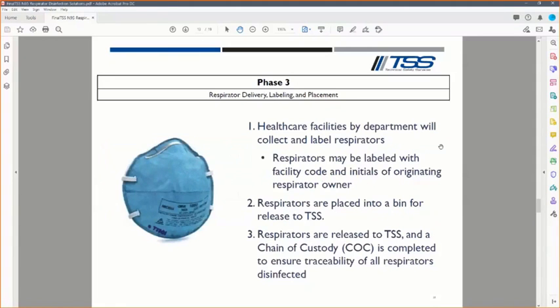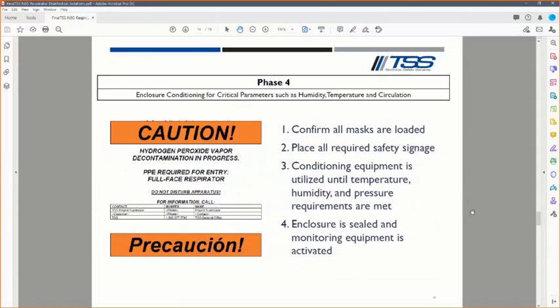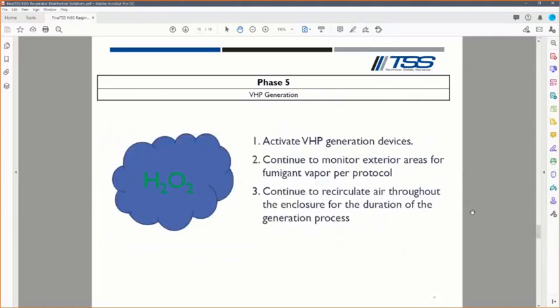The collected and labeled respirators are, of course, brought to the unit, released with that COC. During the disinfection, we make sure to label. Of course, there's a vaporized hydrogen peroxide disinfection in process, and we have a site supervisor on site for the duration. We'll recirculate the air throughout the unit during the VHP to make sure that every mask on every shelf is sufficiently exposed, and we have biological indicators placed throughout the entire unit, along with chemical indicators for a real-time result. And we also monitor the VHP ppm in real time.